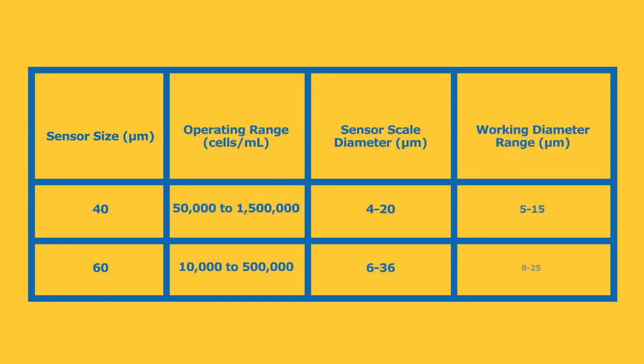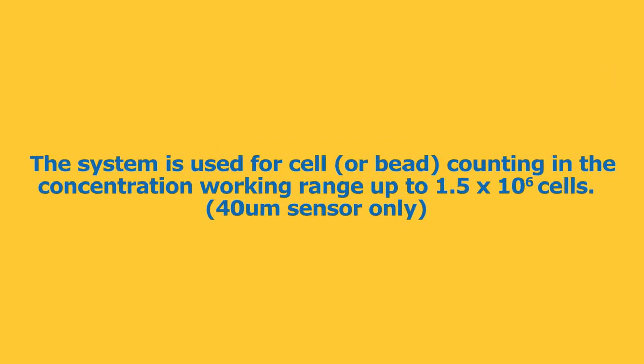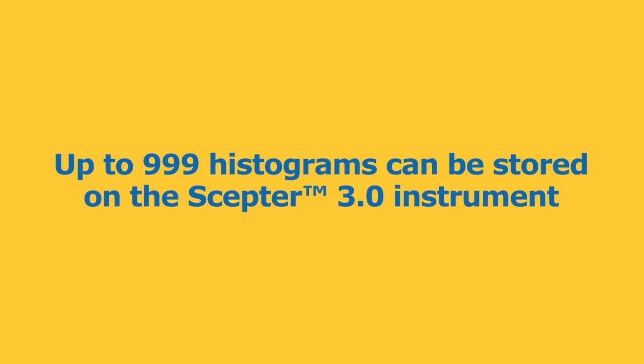The system is used for cell or bead counting in the working range of 5 to 25 micron diameters and concentration working ranges up to 1.5 times 10 to the 6. Up to 999 histograms can be stored on the Scepter™ 3.0 instrument.